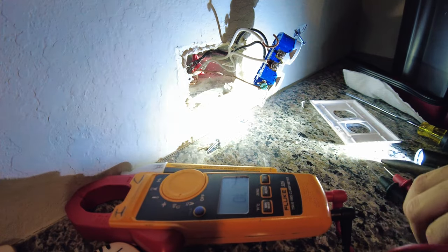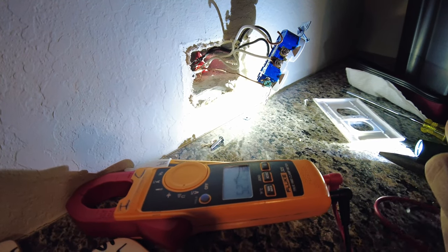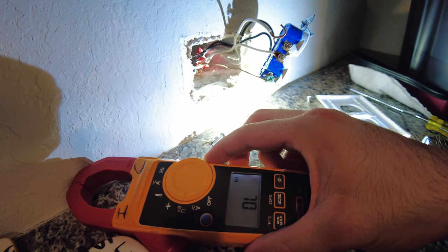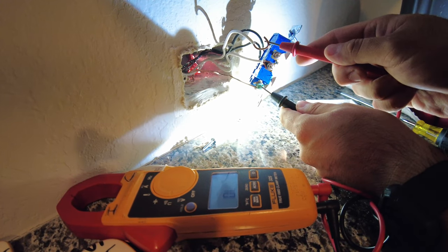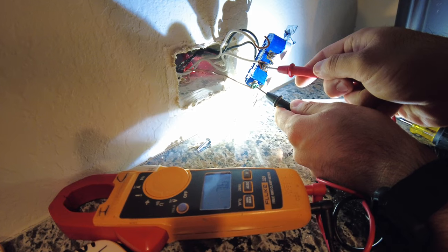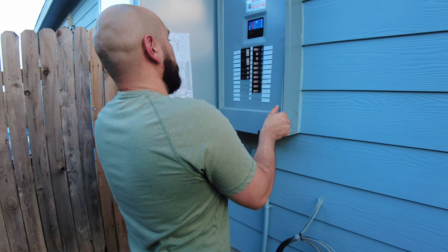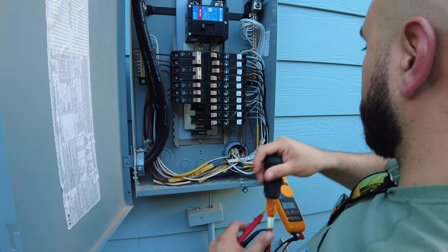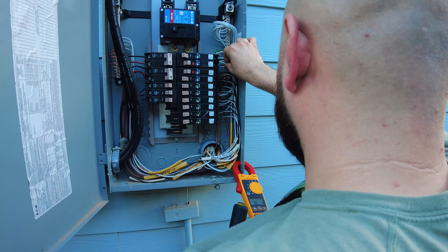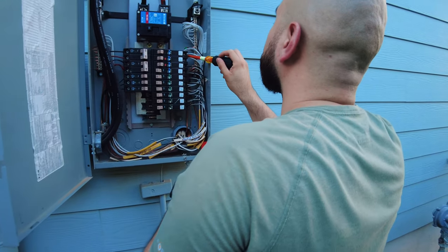The next step is to isolate the fault. This receptacle is the first device in line, so what I did was disconnect the neutral feeding the other receptacles and left the wire feeding this receptacle connected, just to see if the fault remained or cleared. I found out the wire feeding this receptacle still has a ground-to-neutral fault, which is making me think it's the breaker and not a fault on a specific device.